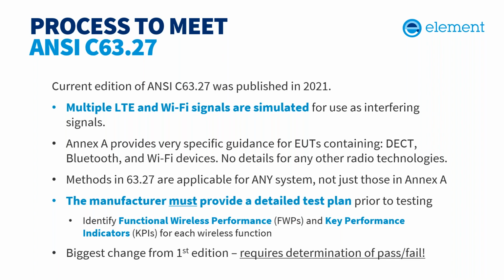A test plan is required prior to testing. It's going to be separate from your 60601 test plan because the risks are different and the tests are significantly different. AAMI TIR69 lays out the risk analysis for coexistence. You're going to need to identify functional wireless performance and key performance indicators, things like jitter, bitrate, throughput, etc. How does that affect overall performance of the medical device based on your wireless performance? Failure criteria need to be determined by a manufacturer during the risk assessment, and it's not something a test lab can really do without in-depth knowledge of the medical device, which we're just not going to have.